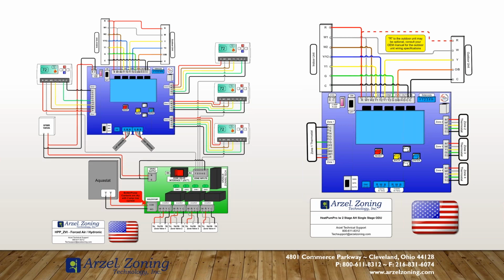Now the AirBoss does have a switch on it that says master zone. It's also set of contacts, say stat setback. So the question being, do you have a master thermostat? Which one is it? The answer to that is simply there are no master thermostats. The AirBoss allows for a feature called master zone, in which if that is set to on, or if the stat setback terminals are closed, so you have a timing switch. This is more popular for commercial application. When those contacts are closed, Zone 1 thermostat controls everything. Zones 2 through 8 would be ignored with the AirBoss.